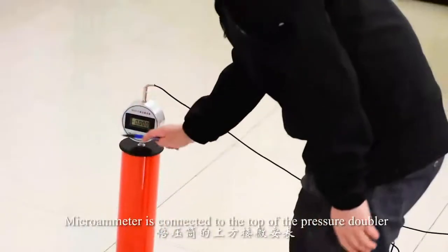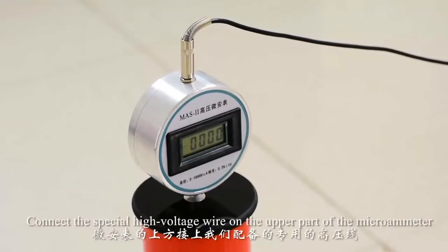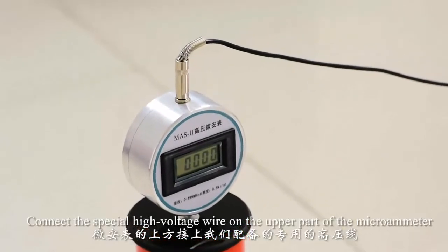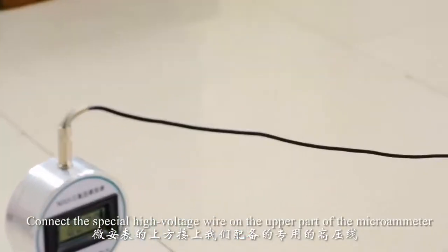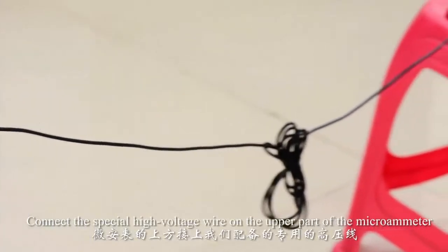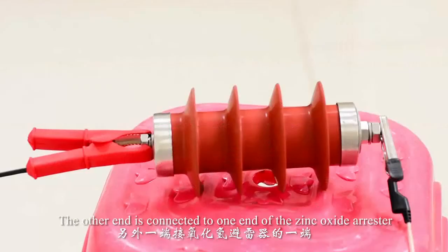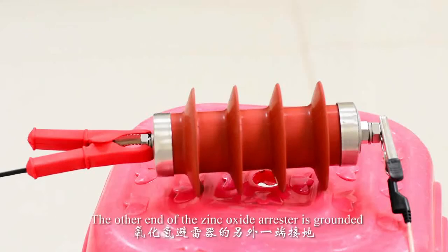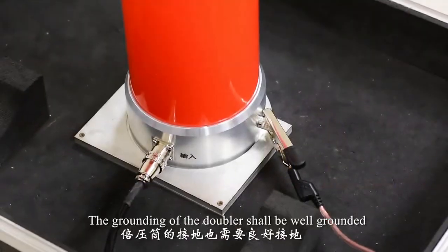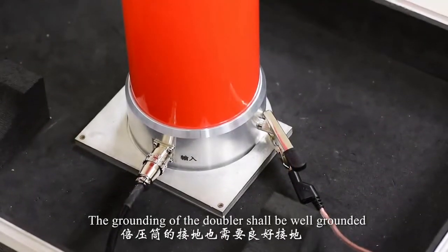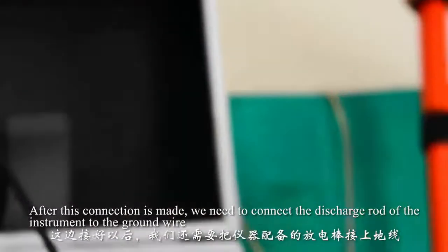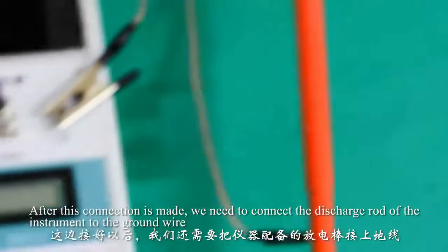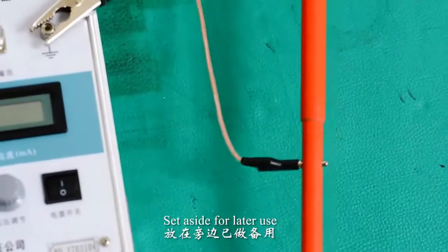The microammeter is connected to the top of the doubler. Connect the special high voltage wire on the upper part of the microammeter. The other end is connected to one end of the zinc oxide arrestor. The other end of the zinc oxide arrestor is grounded. The doubler shall be well grounded. After this connection is made, we need to connect the discharge rod of the instrument to the ground wire and set it aside for later use.